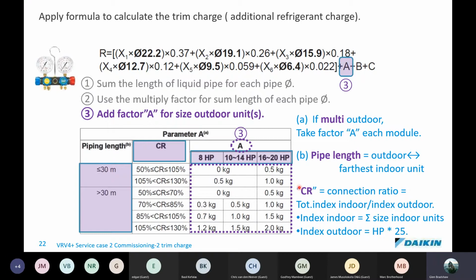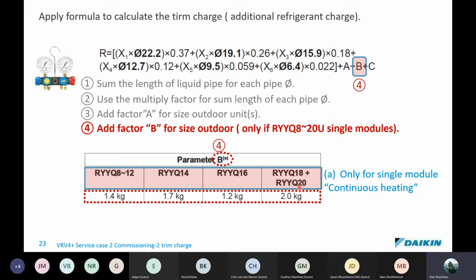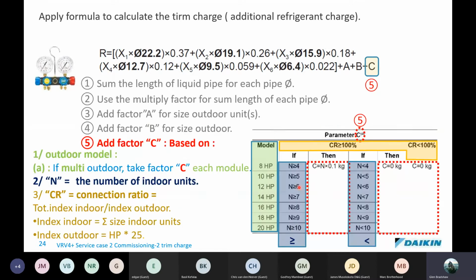All right, then you may also see on the calculation sheet an amount for a unit RYYQ. Ignore this amount because we don't bring these units into the country. And then, of course, there's an amount that is based on the number of indoor units. Once all of this is calculated together, we get a total amount of kgs that were required to be able to add to the unit on top of the factory charge.